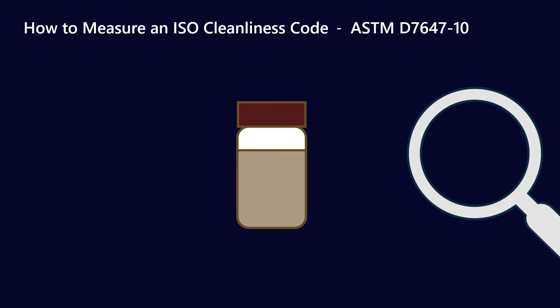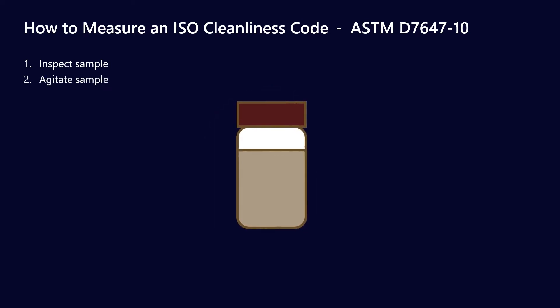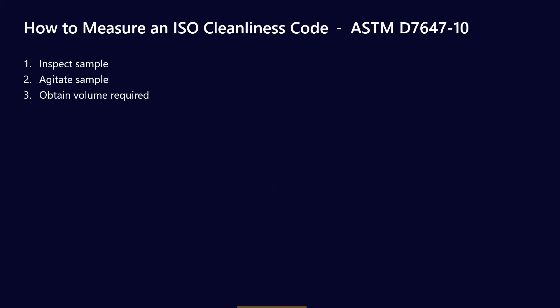Step one: get your sample and do an inspection. I've covered why you would do an inspection in a previous video — effectively it's to look for contaminants, water, etc. Step two: agitate the sample to make it homogenous. Step three: obtain the volume required for the cleanliness code test. Remember, on this oil sample we're probably running a whole bunch of tests — ICP, FTIR, etc. — so just the volume that we need for the cleanliness test.